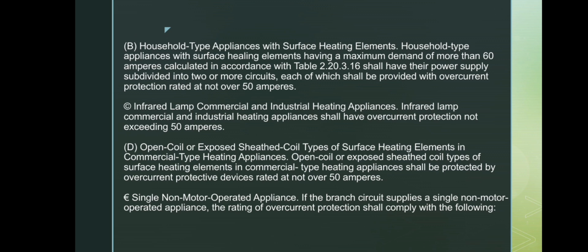Third, if we're dealing with open coil or exposed sheathed coil heating elements in commercial appliances, these must be protected by a device rated not more than 50 amperes as well. And finally, if the branch circuit supplies only one non-motor operated appliance, its overcurrent protection must follow the specific rating required for that appliance.